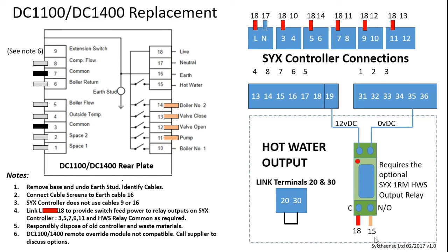Boiler number 1 can now be moved from terminal 10 on the DC controller and connected into terminal 4 on the SYX controller. If you have a second boiler, terminal 14 can be disconnected and connected into terminal 6 on the SYX controller. The pump on terminal 11 can be moved onto terminal 8 of the SYX. Valve open, if you have a VT valve, can be moved from terminal 12 and moved into terminal 10 on the SYX controller. Valve close can be moved from terminal 13 and moved into terminal 12. That completes the mains voltage connections from the DC onto the SYX controller.